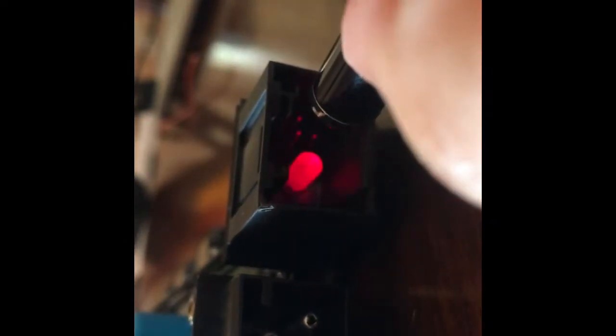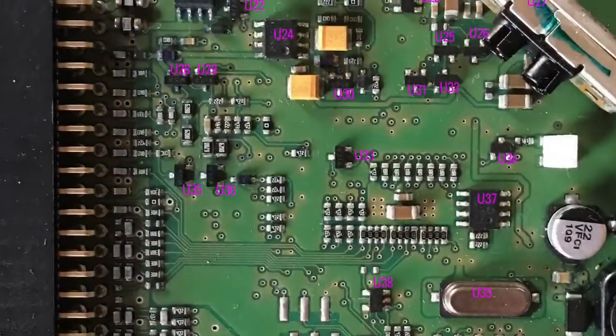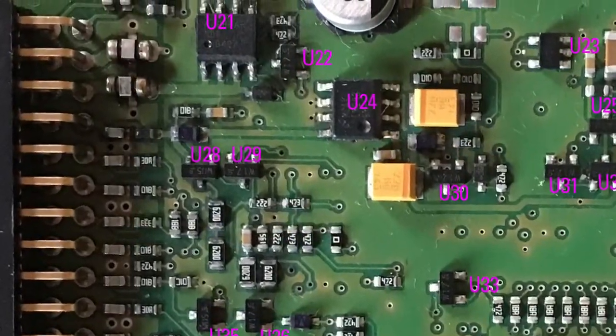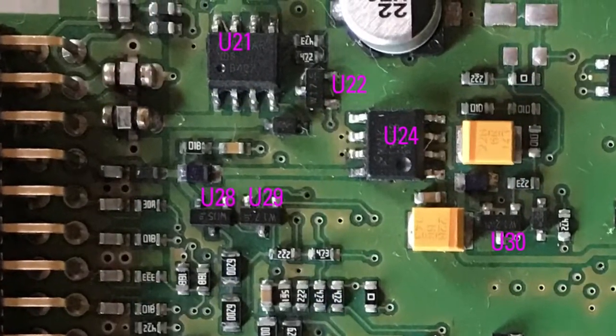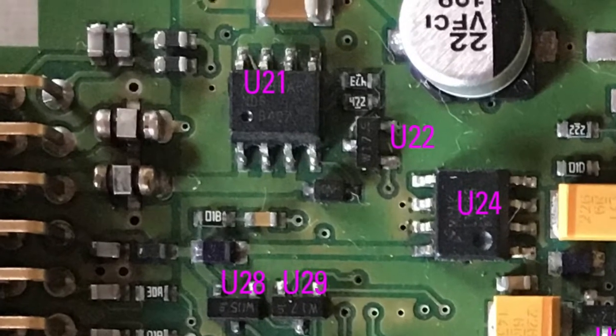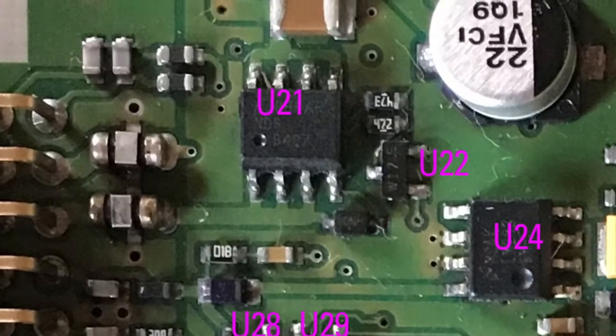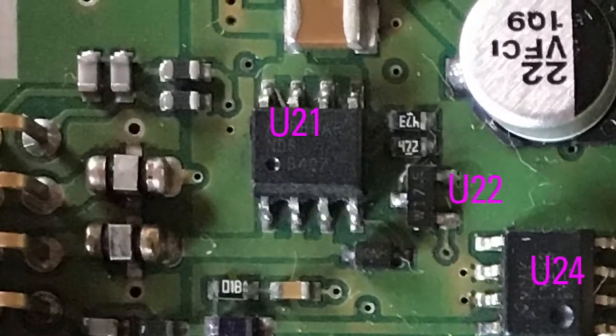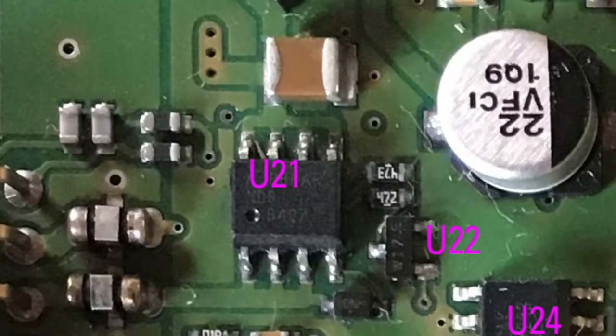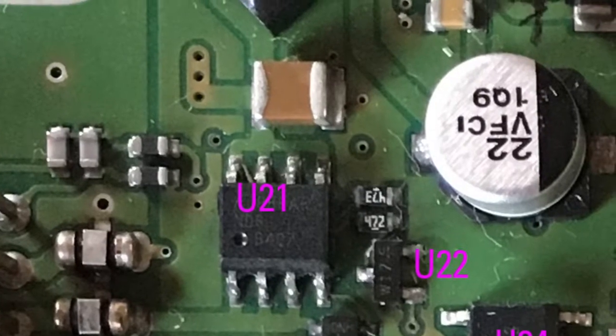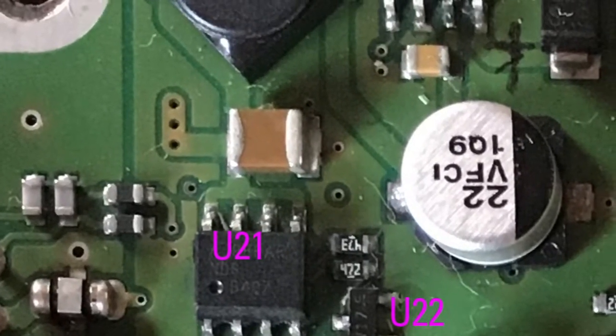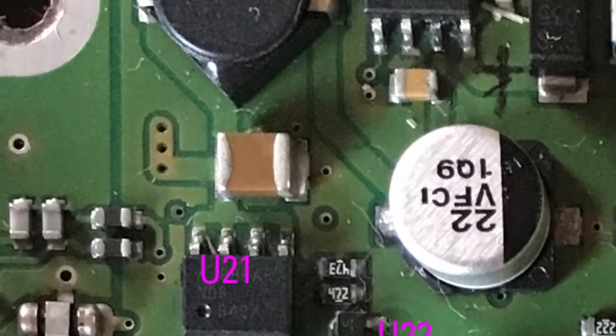When the light is going inside the fiber optic transceiver, you should read 0V on the gate of U21, and consequently, the drain of the MOSFET shall go to 12V. The input voltage of U20, U12, U2, and U9 shall be 12V.